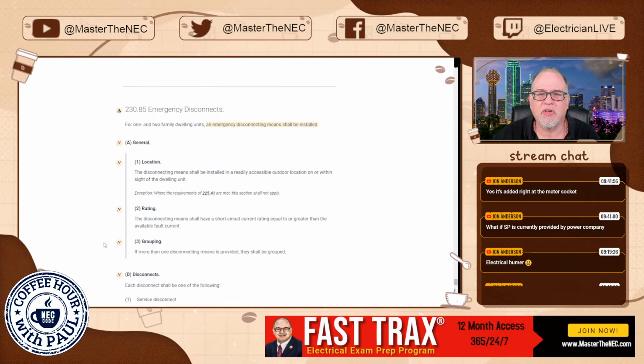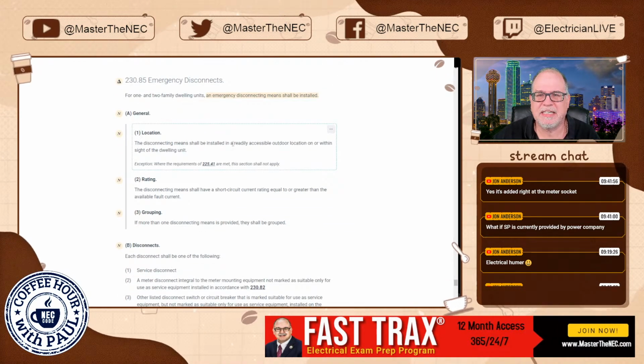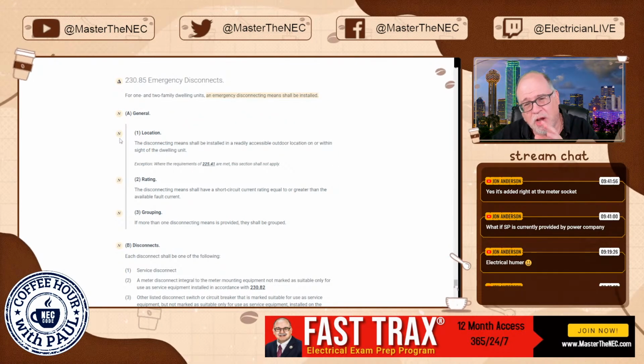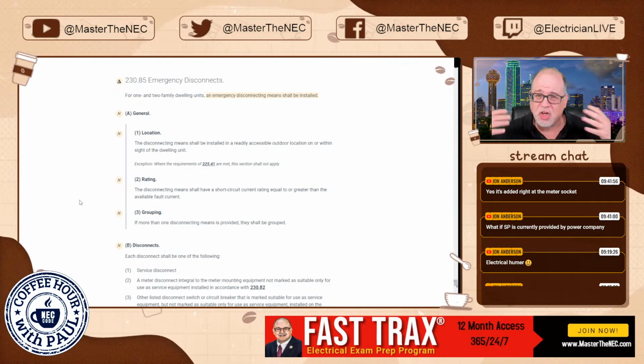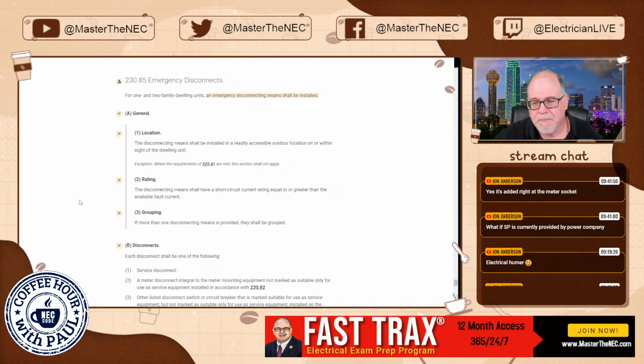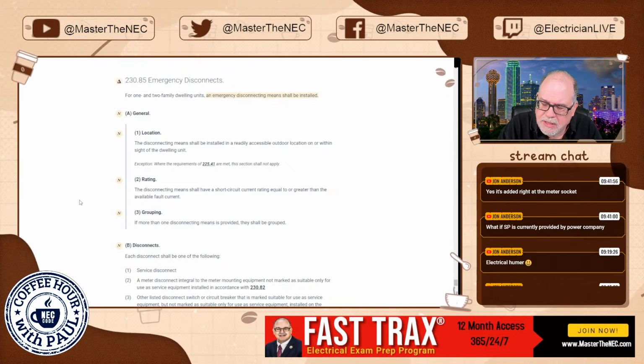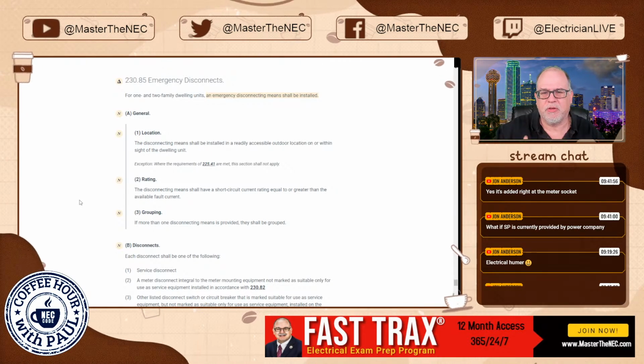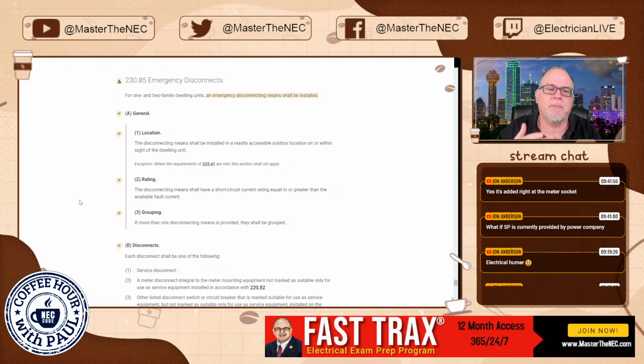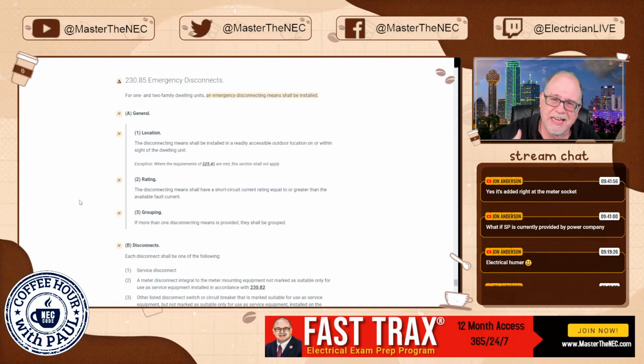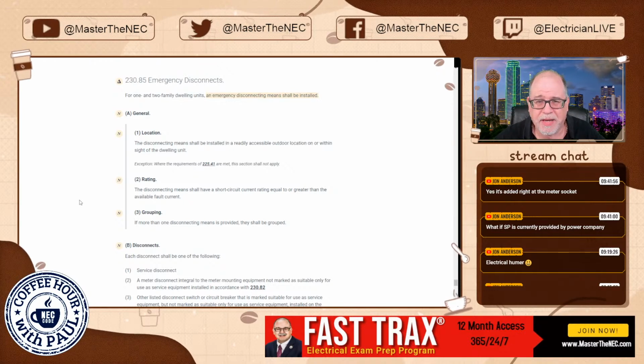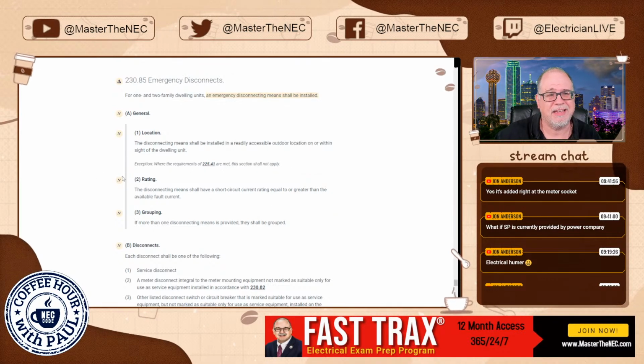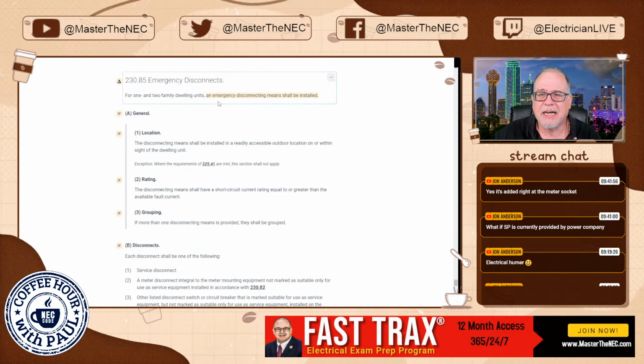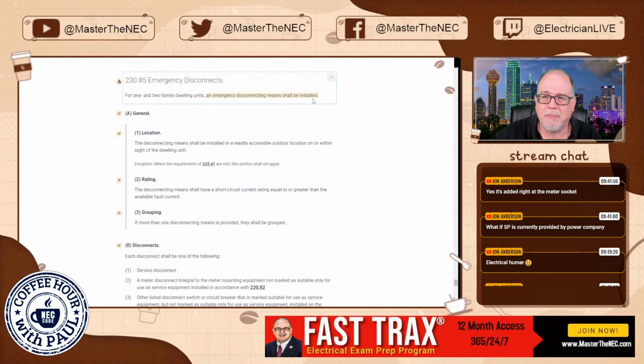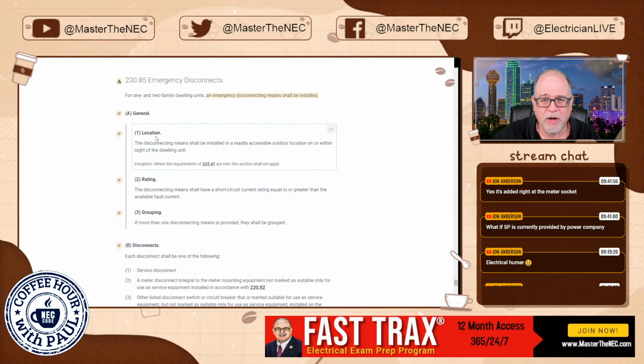All right, so here's your 230.85 emergency disconnect rule. Now, again, see all these ends? This kind of looks like it's all new. But no, what it's done is break it out. So it's much easier to understand. And I like this. I think it's better, the direction that they've gone here. All right, so again, the emergency disconnect means shall be installed, general. Where is it to be installed?